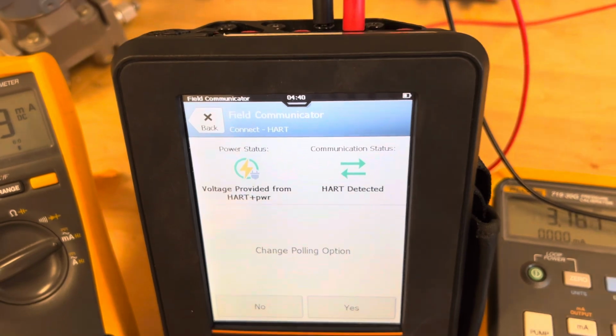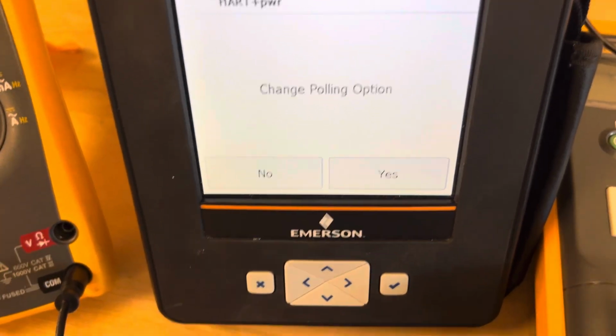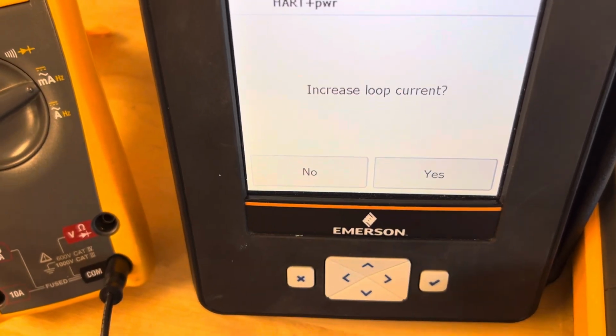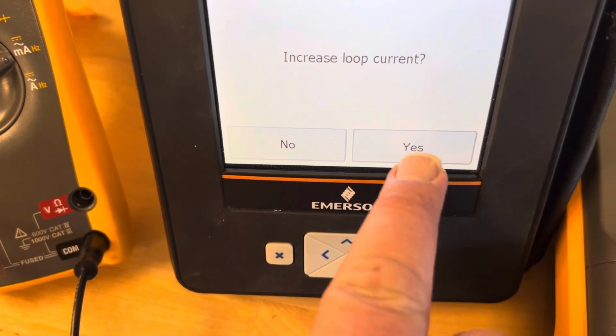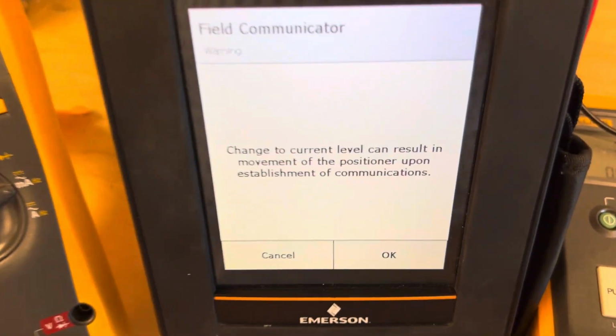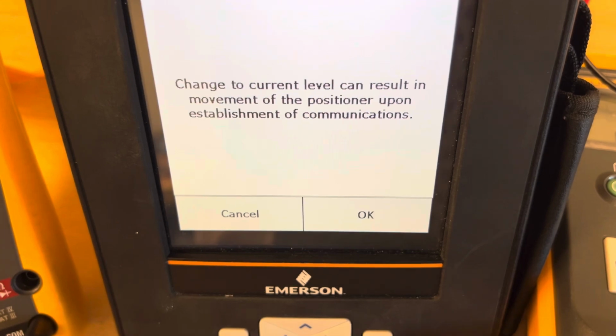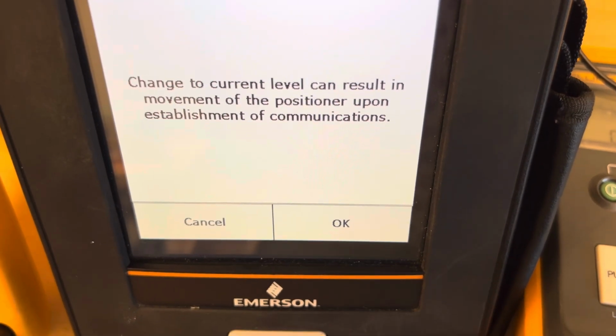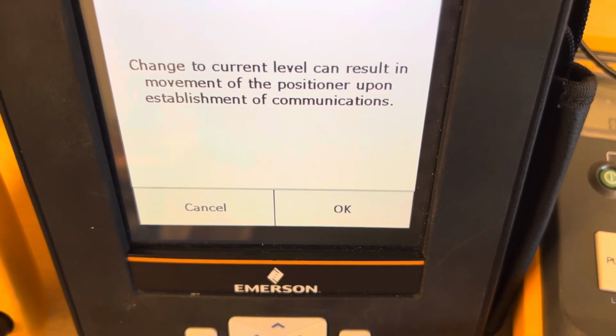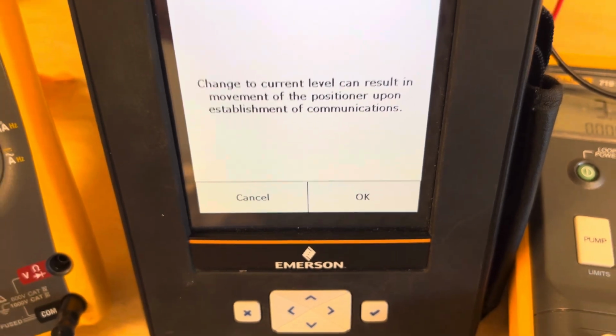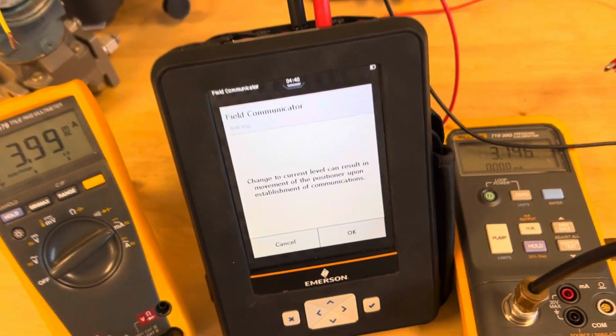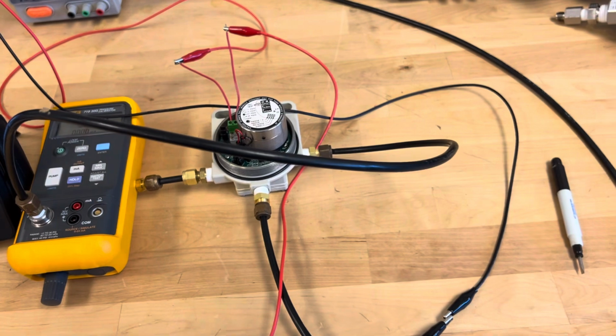All right, now it's going to ask me, do you want to change polling options? I'm going to say no. Increase loop current, I'm going to say yes. It gives a warning that changing the current level can cause the positioner to move the valve. Well, we're not connected to a valve today, so we're not going to be concerned about that.